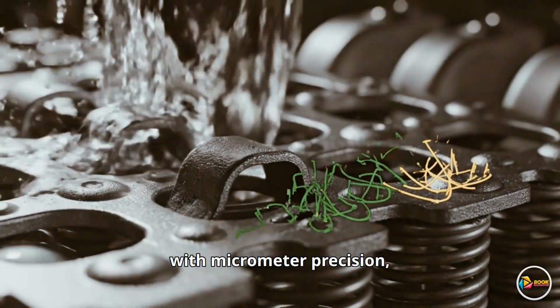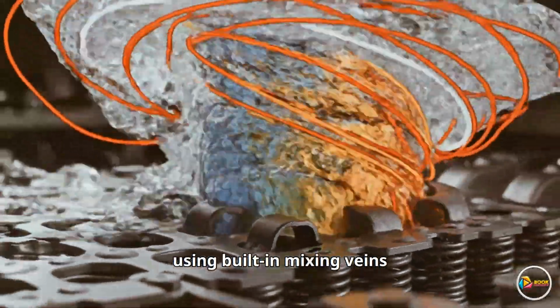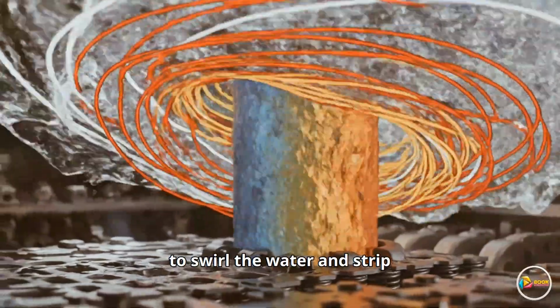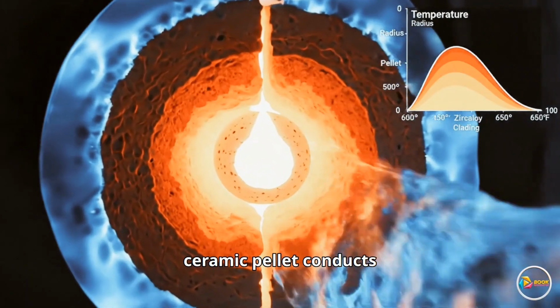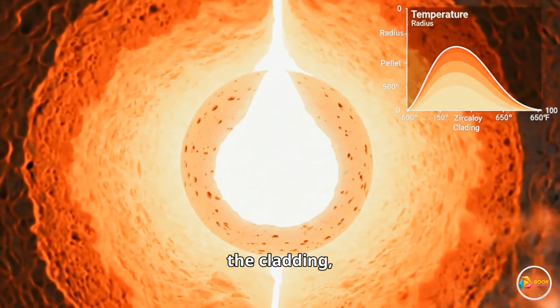Specialized spacer grids hold each rod with micrometer precision, using built-in mixing vanes to swirl the water and strip away heat with maximum efficiency. Heat generated inside the ceramic pellet conducts across the helium gap and into the cladding, transferring millions of British thermal units.